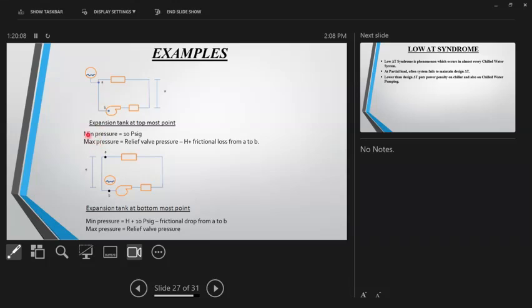So I will call this P1 and this P2, and I'll put these values in that equation. Now it can happen that the expansion tank is in the basement itself. So what is the minimum pressure in the tank? I know that I want 10 psig minimum pressure at the highest point. So 10 psig is here, plus H. Now in the expansion tank, there's 10 plus this H.